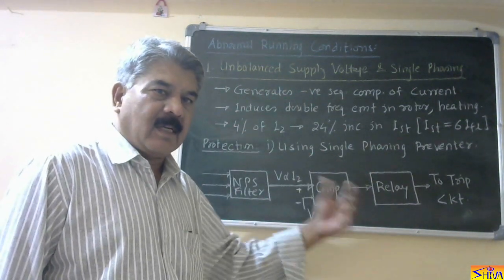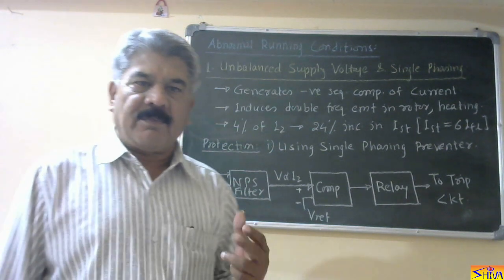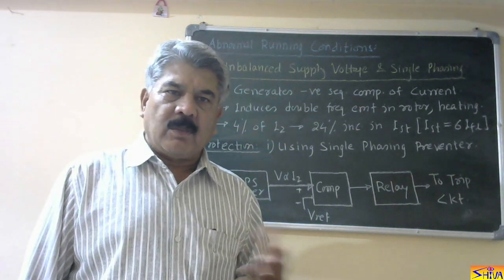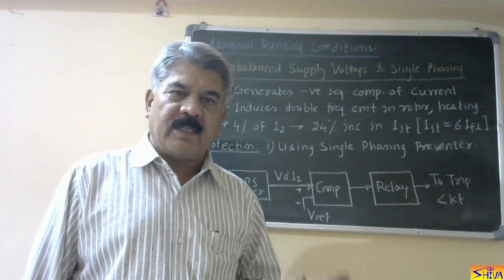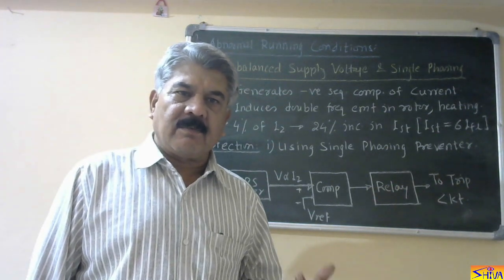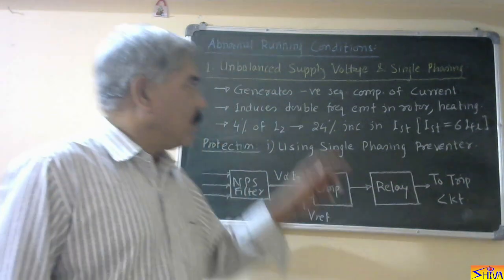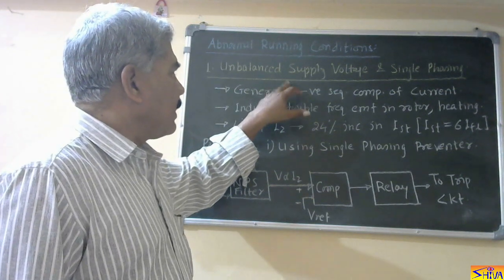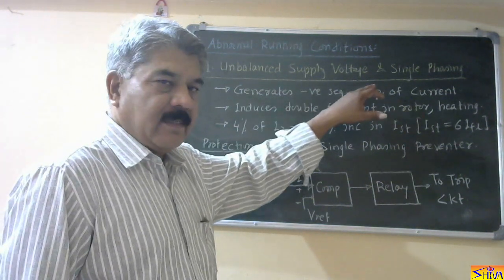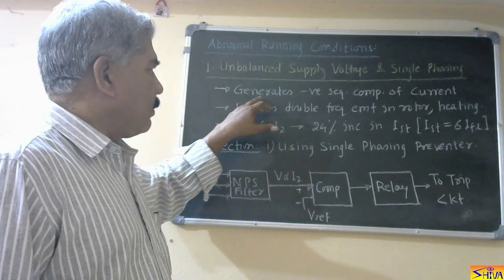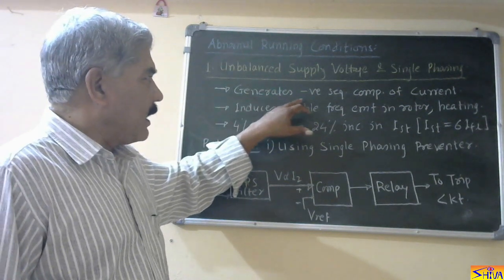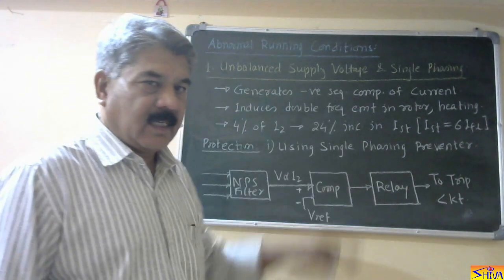Same thing is with single phasing. Single phasing means out of three phases, one phase goes. So that is also an unbalanced condition. Two phases are there and one phase is giving zero voltage. So these two conditions, unbalanced supply voltage and single phasing, are the same. During these conditions, a negative sequence component of the current is generated.